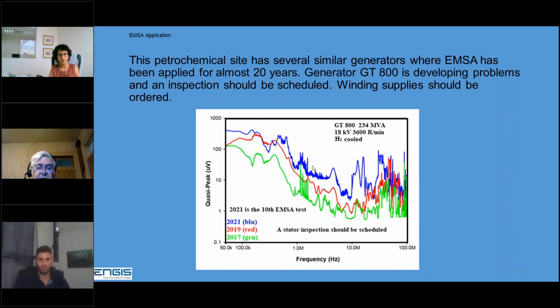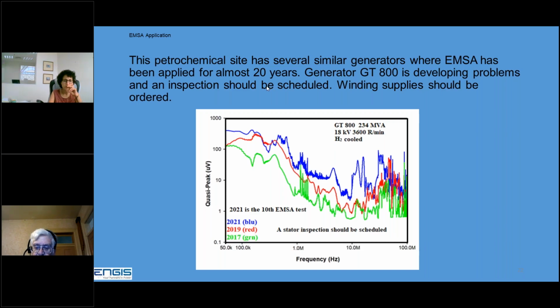This part here describes what's in the slots. This part here describes what's in the end windings. This part over here describes the isophase bus. So it looks like they have loose end windings and they have stator bars that are loose in the slots. So they need to schedule an inspection and probably make some winding repairs.